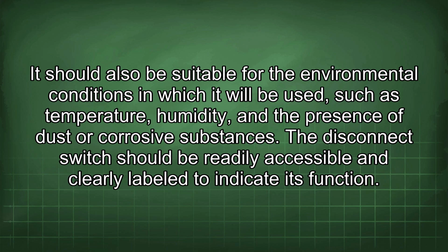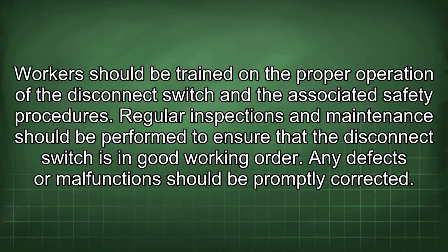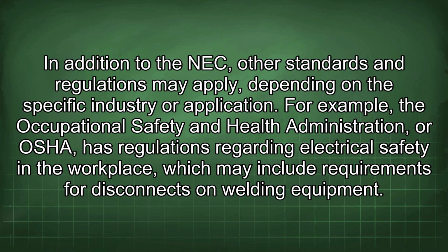The disconnect switch should be readily accessible and clearly labeled to indicate its function. Workers should be trained on the proper operation of the disconnect switch and the associated safety procedures. Regular inspections and maintenance should be performed to ensure that the disconnect switch is in good working order. Any defects or malfunctions should be promptly corrected. In addition to the NEC, other standards and regulations may apply depending on the specific industry or application. For example, the Occupational Safety and Health Administration, or OSHA, has regulations regarding electrical safety in the workplace, which may include requirements for disconnects on welding equipment.